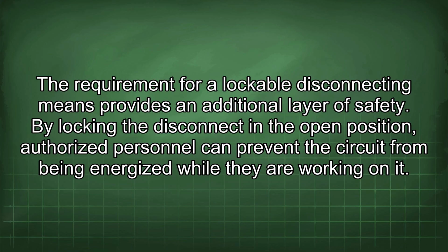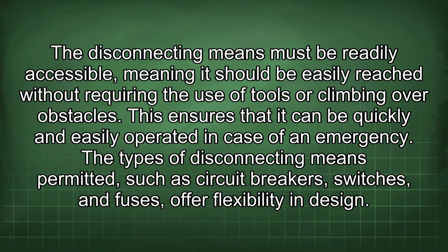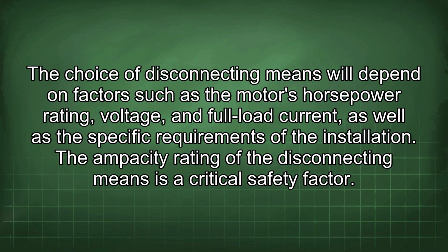The disconnecting means must be readily accessible, meaning it should be easily reached without requiring the use of tools or climbing over obstacles. This ensures that it can be quickly and easily operated in case of an emergency. The types of disconnecting means permitted, such as circuit breakers, switches, and fuses, offer flexibility in design. The choice of disconnecting means will depend on factors such as the motor's horsepower rating, voltage, and full load current, as well as the specific requirements of the installation.